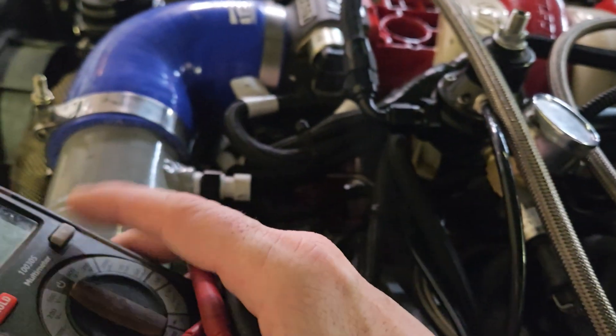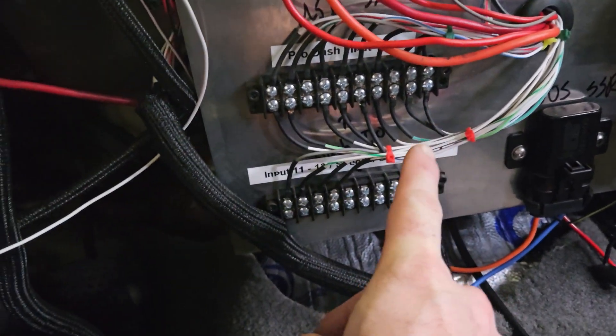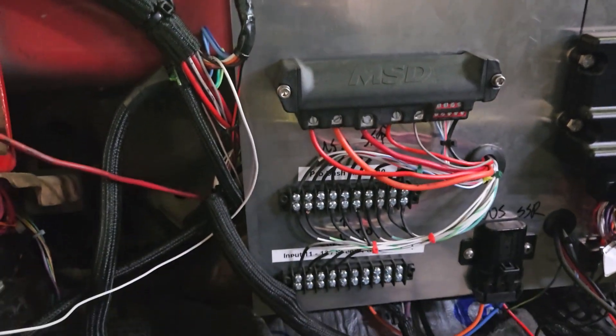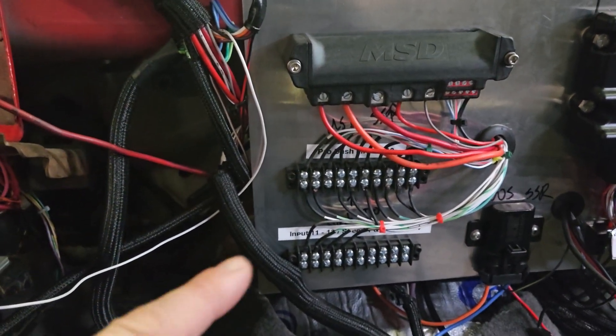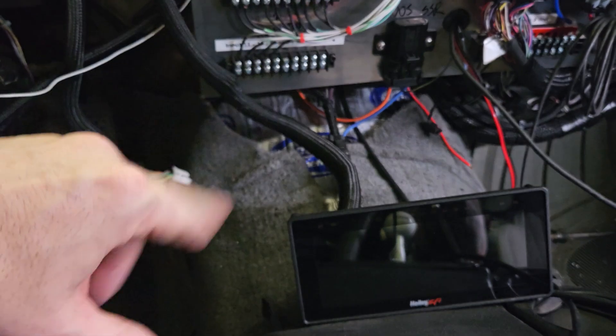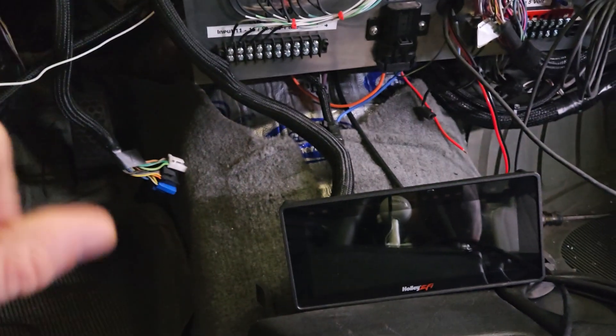We would also have you read at the back of the plug — if possible, if you have a setup like mine where each sensor is on a terminal strip, it would be really easy to test there as well. That's going to eliminate any potential wiring issues. The sensor itself may actually be reading 7,000, 9,000, 10,000 ohms — whatever it is for that temperature — but up at the Prodash there could be an open circuit or short circuit giving you a false reading. Verifying the sensor resistance both at the sensor and up at the plug, and eliminating the possibility of bad wiring, a failed crimp, or failed solder, will aid a lot in troubleshooting your system.